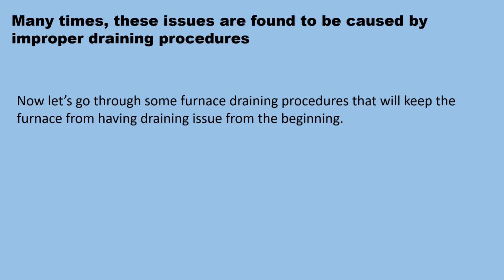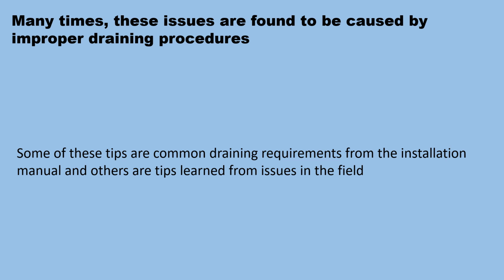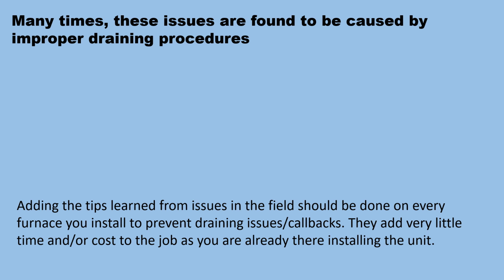Now let's go through some furnace draining procedures that will keep the furnace from having draining issues from the beginning. Some of these tips are common draining requirements from the installation manual, and others are tips learned from issues in the field. Adding the tips learned from issues in the field should be done on every furnace you install to prevent draining issues and callbacks. They add very little time and or cost to the job as you are already there installing the unit.